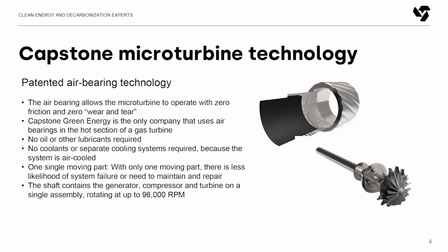That means there's no oil, no coolants, no lubricants of any kind. It's just naturally drawing air down the shaft and creating lift that allows the turbine and the two-pole permanent magnet generator to spin freely on air. Capstone is the only company that does this. And inherently, that single moving part spinning on air bearings makes it a very low-maintenance, highly reliable product that's very easy to service.